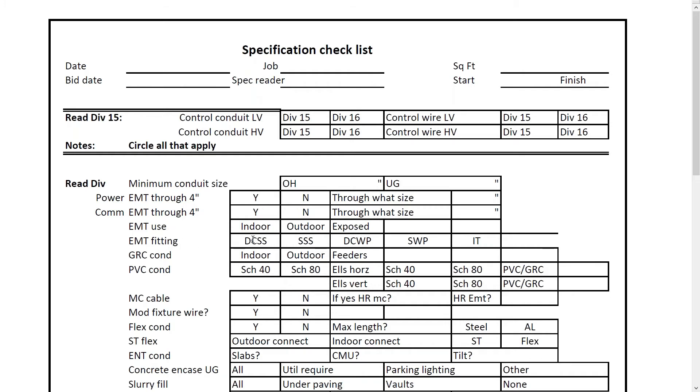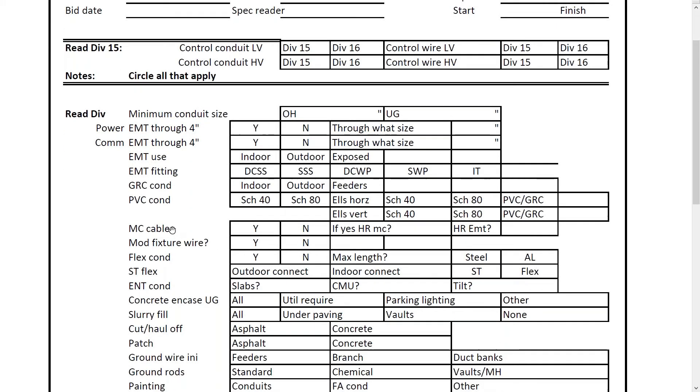Here's EMT fitting options: die-cast set screw or set screw steel, die-cast weatherproof which is your compression type. Sometimes, especially when bidding government — city, state, or federal — jobs, they require compression fittings. There's also insulated throat; if insulated throat is required, you need to know that because there's a price difference. On some jobs, MC cable is not allowed, so you just circle yes or no. It also asks whether home runs in MC cable are allowed. Here's ST flex — that means seal-type flex — sometimes required for both indoor and outdoor connections.